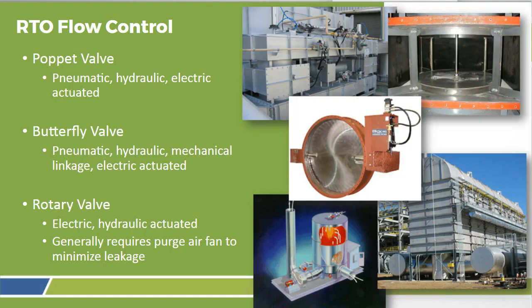Additionally, we talked a little about flow control. That's a really crucial part of the multi-chamber or the regenerative thermal oxidizer. So there's different ways to do it. You have the poppet valve or a standard butterfly valve. You can see on the bottom right is a large unit with butterfly valves. Exhaust manifold on the right, inlet on the left side on the bottom there.